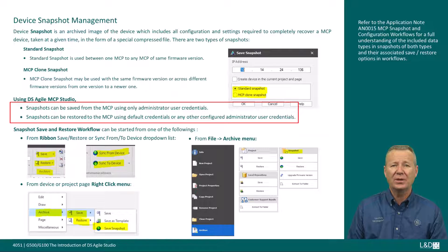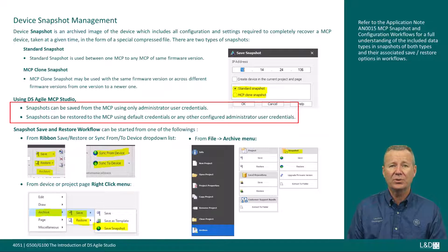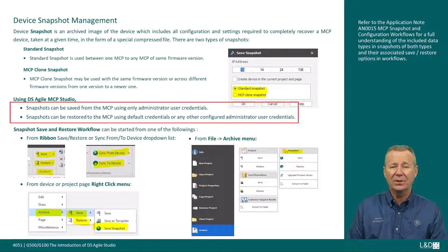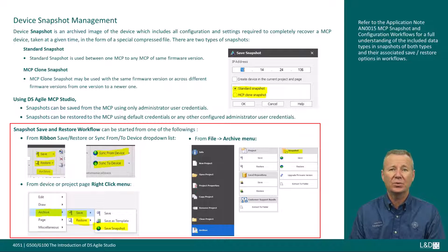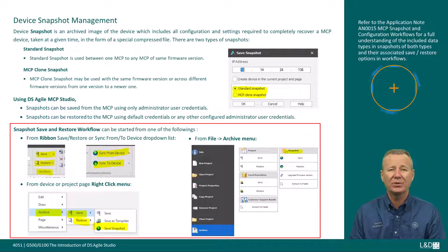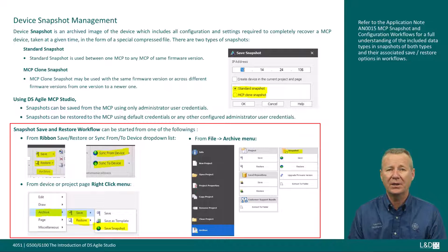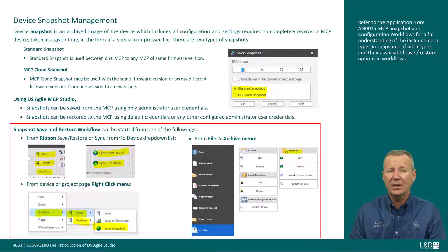Using DS Agile MCP Studio, snapshots can be saved from the MCP using only administrator user credentials. Snapshots can be restored to the MCP using default admin credentials or any other configured administrator user credentials. The snapshot save and restore workflow can be started from the ribbon archive save/restore or sync from/to device drop-down list, from device or project page right-click menu, or from the file archive menu. Refer to application note AN0015 MCP Snapshot and Configuration Workflows for full details.